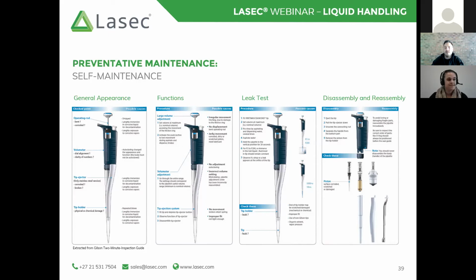So it is incredibly important before starting with the pipette to do a general appearance check. This is to identify if there are any glaring defects with the exterior of the pipette. All right, so maybe the tip ejector is missing, there's a crack in the tip holder, maybe the volume setting has been overwound, so you are seeing 3 zeros instead of a number. This is a general appearance check that you could do relatively quickly and identify, is this pipette going to be suitable to use or not?